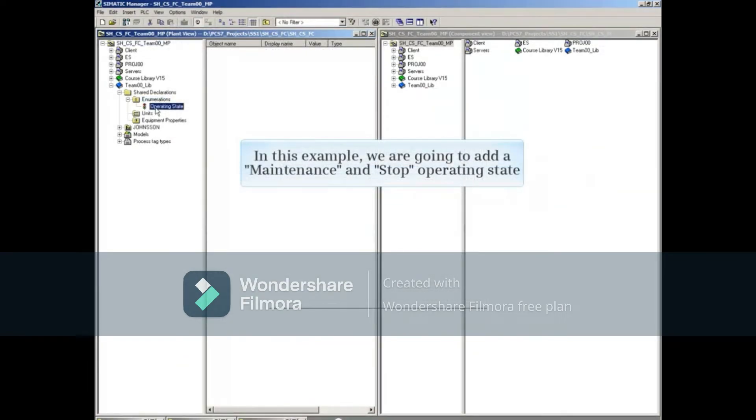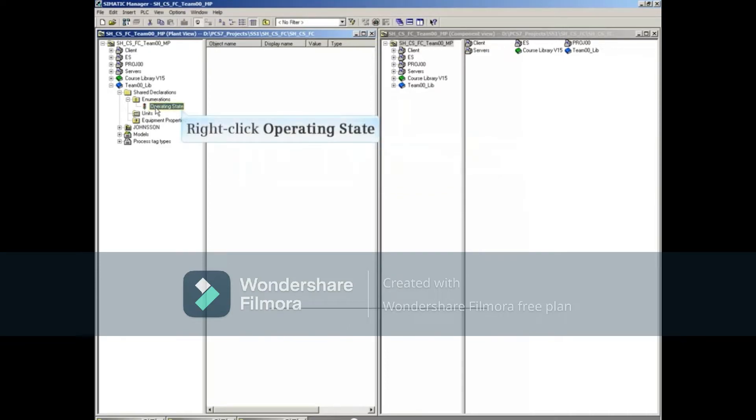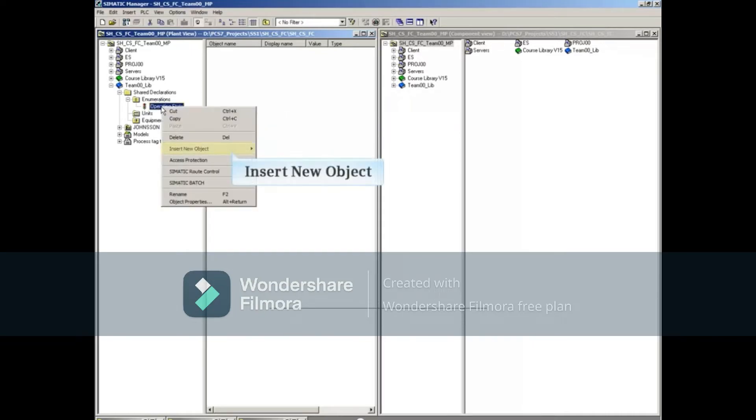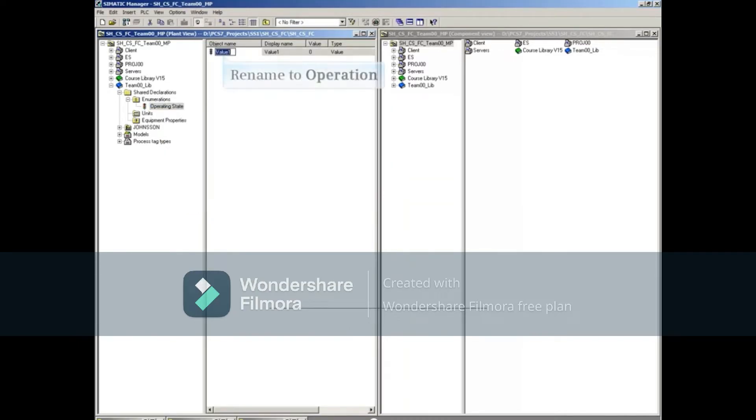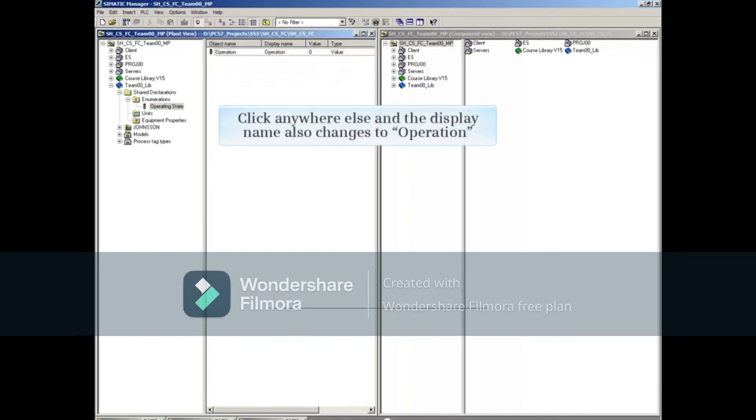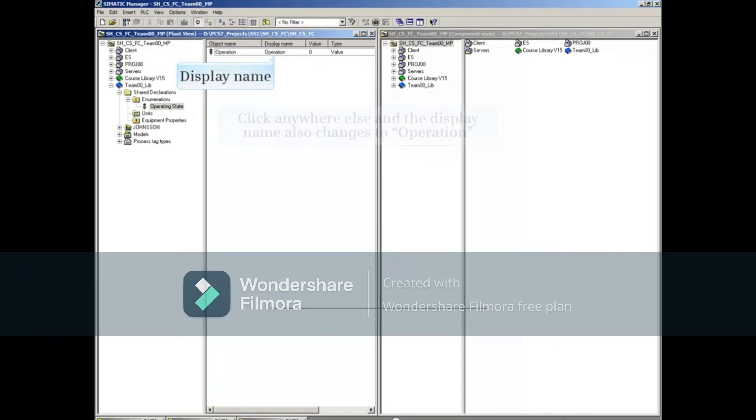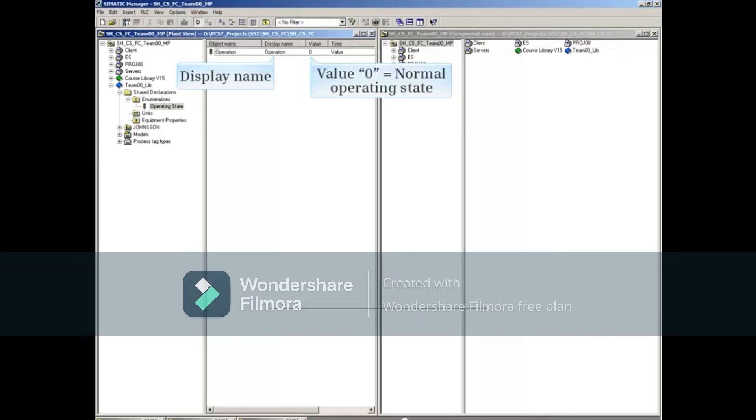In this example, we're going to add a Maintenance Operating and a Stop Operating State. Right-click Operating State, select Insert New Object, and then select Value. Rename the new value object to Operation. Click somewhere else, and the display name will also change to Operation. This will represent the normal operating state of the process with the value of 0.